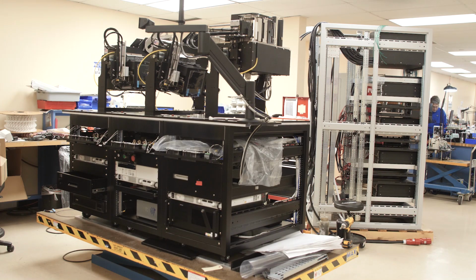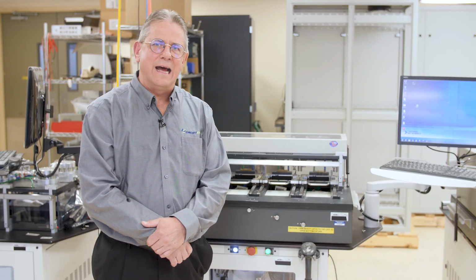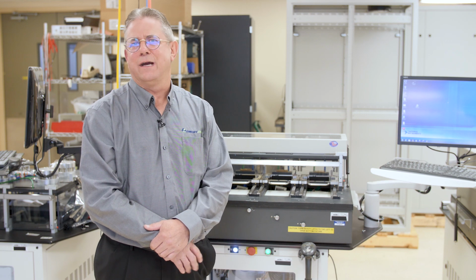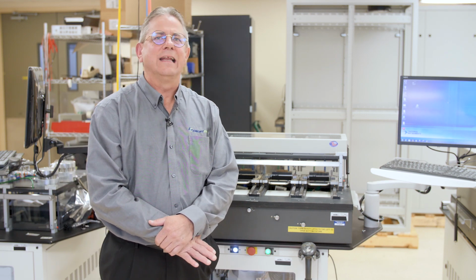One thing about racks we've found, especially with taller racks: make sure you understand how much weight is going into that rack. A lot of times this is where people want to cut corners. We built a rack, built to print, with lots of heavy power supplies and equipment. We went to pull out the power supply in the bottom and couldn't get it out, because the whole bottom of the rack oil-canned under the weight of the test system. The rack is not a place to cut corners - please make sure it's rated for at least as much, if not twice as much, as you want to use.